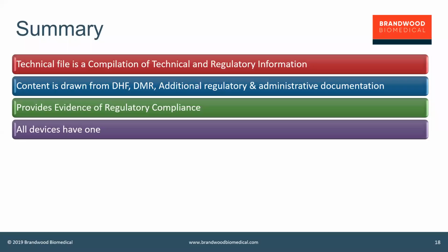Every device needs one. So again, it's not a nice to have, and it's not a, well, we've got a couple of documents, so that's a technical file. No, ISO 13485 requires that there is a technical file created for every medical device. In addition, if you have a medical device that's regulated by any regulator, they're going to expect a technical file to support that.